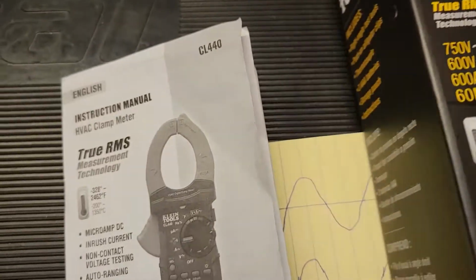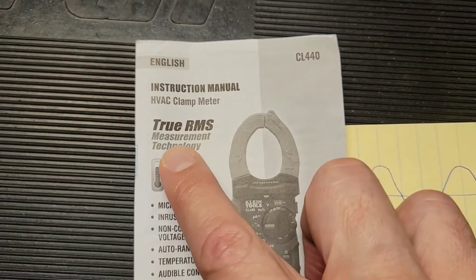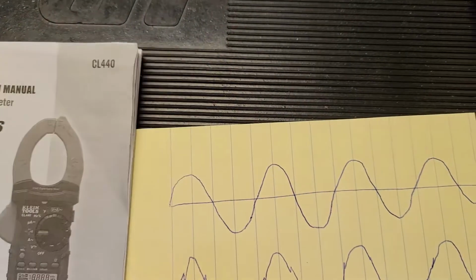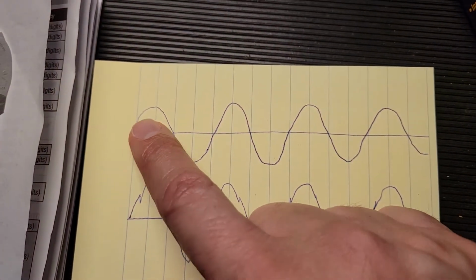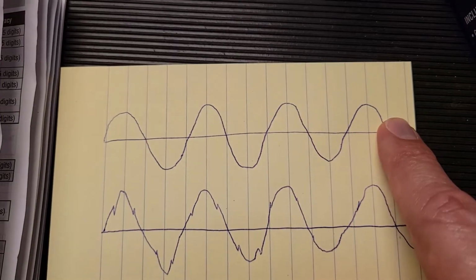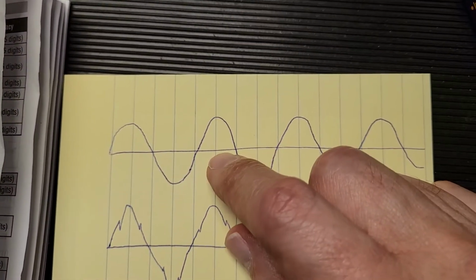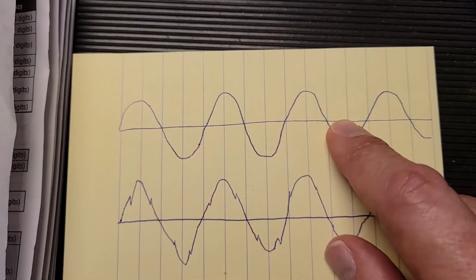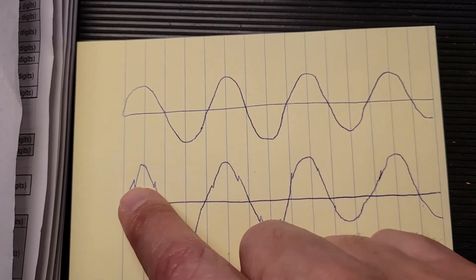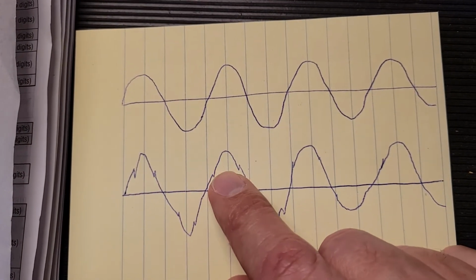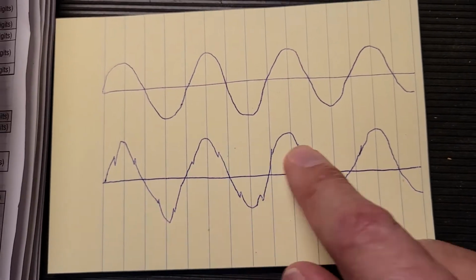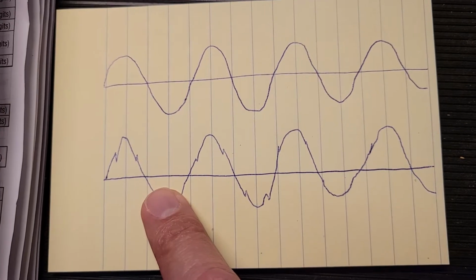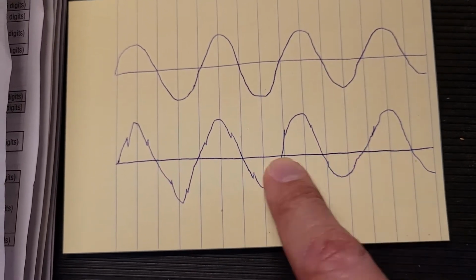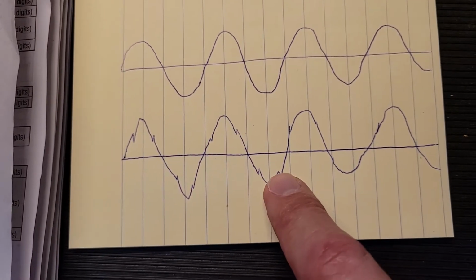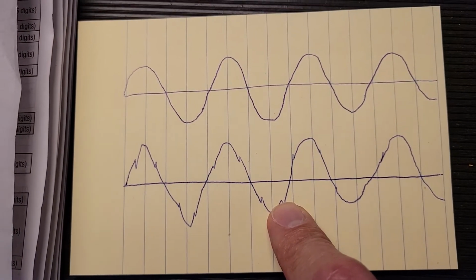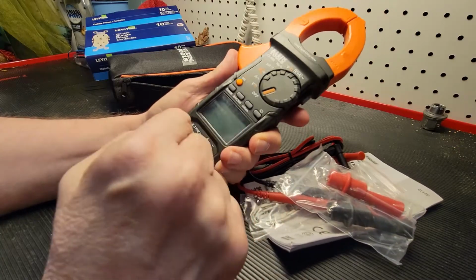In both the box and the manual, it mentions True RMS measurement technology. To simplify it, what that means is when you have a sinusoidal wave, as AC current is, when you measure that, you get your reading. All multimeters and AC clamps can do a great job of that. But when there's a device that corrupts that wave and puts irregularities into it, multimeters and non-True RMS meters will give you a false reading because they can't compensate for those irregularities, as a true RMS meter can. We're going to explore all these symbols and what all this stuff means.